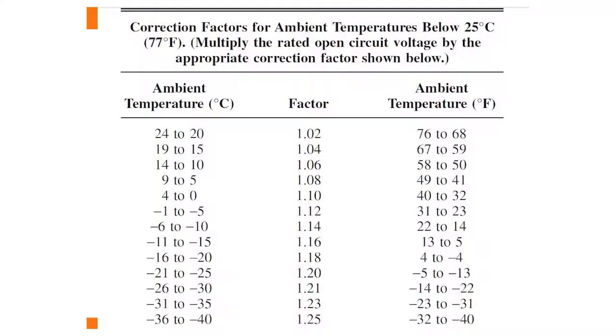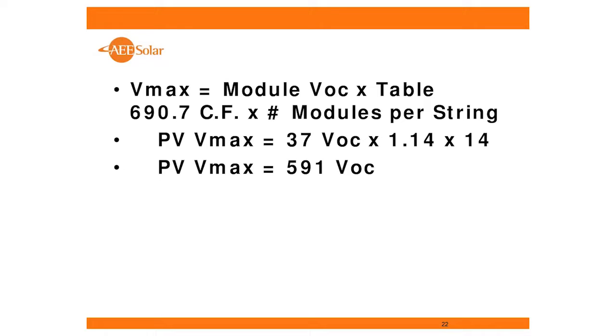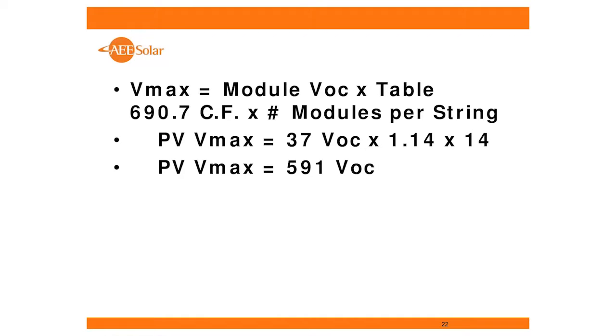If you use this table, you are going to be more conservative than the actual need. And there's nothing wrong in the code with having things more conservative. Code's very conservative about a lot of things as a basic calculation. So in the 2017 code, this is added back in as you can apply it to any crystalline silicon system, and if the calculation works for you, there's no problem with using it. And so there's the calculation for, by the way, these slides are going to be available after the show to download, so don't worry about taking too many notes here. But this is a calculation using the table, a similar calculation using the coefficient.